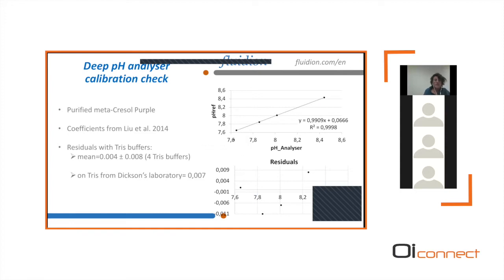So we checked the calibration of our analyzer. This analyzer is running with purified metacresol purple, and we use the coefficients from the literature. We checked this calibration running TRIS buffers, some homemade TRIS buffers, as well as TRIS buffers from the Scripps laboratory. And the discrepancy between the buffers and what was measured being lower than 10 millipH, we decided that there was no need for correction of our instruments.